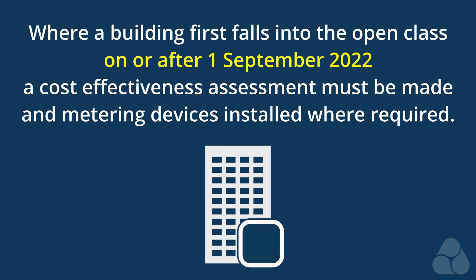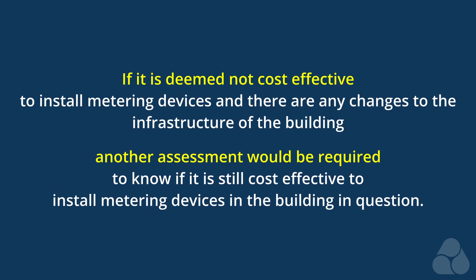Where a building first falls into the open class on or after the 1st of September 2022, a cost-effectiveness assessment must be made and metering devices installed where required. If it is deemed not cost-effective to install metering devices and there are any changes to the infrastructure of the building, another assessment would be required to know if it is still cost-effective to install metering devices in the building in question.